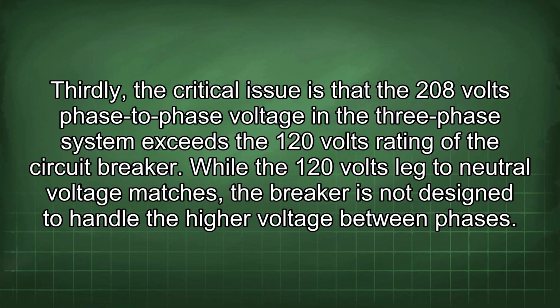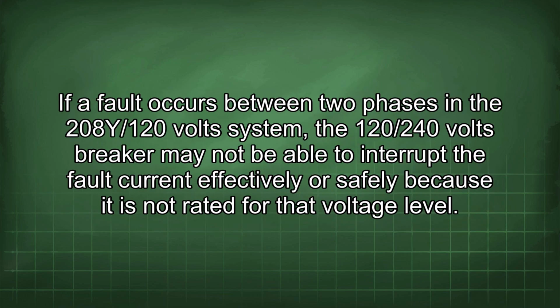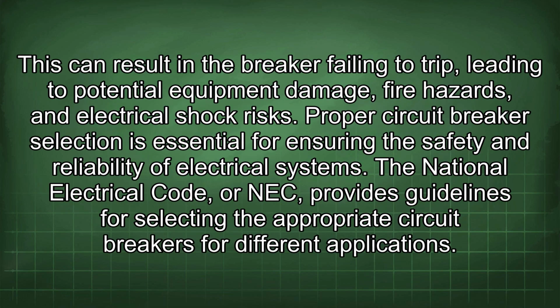Thirdly, the critical issue is that the 208 volts phase-to-phase voltage in the 3-phase system exceeds the 120 volts rating of the circuit breaker. While the 120 volts leg-to-neutral voltage matches, the breaker is not designed to handle the higher voltage between phases. If a fault occurs between two phases in the 208Y/120 volts system, the 120/240 volts breaker may not be able to interrupt the fault current effectively or safely because it is not rated for the voltage level. This can result in the breaker failing to trip, leading to potential equipment damage, fire hazards, and electrical shock risks. Proper circuit breaker selection is essential for ensuring the safety and reliability of electrical systems.